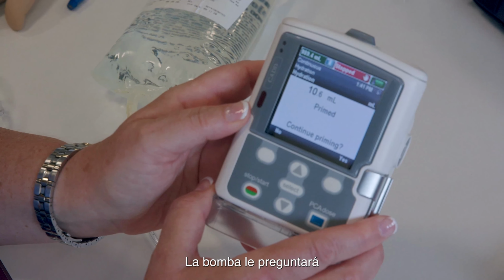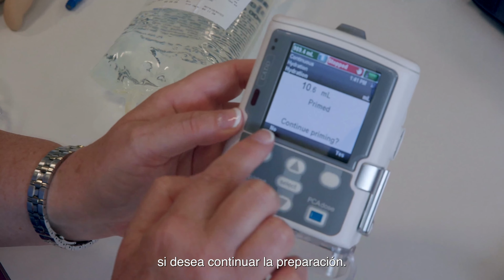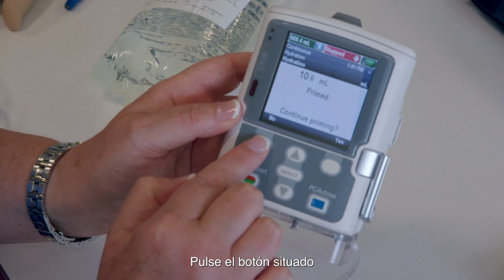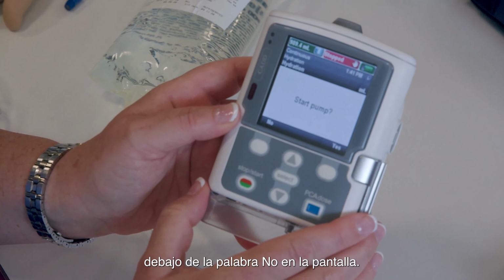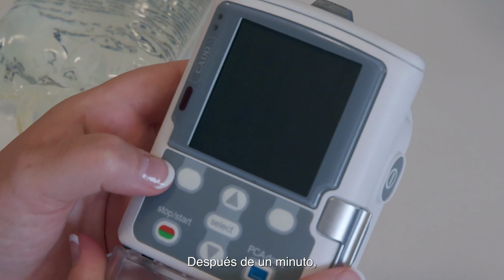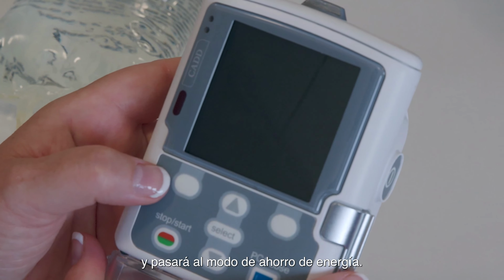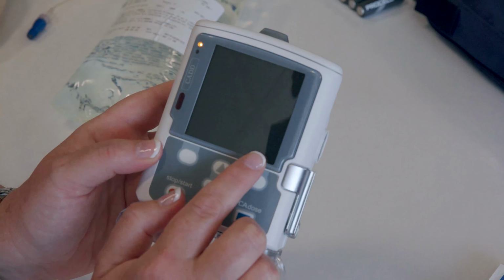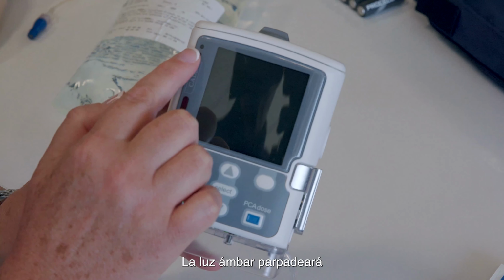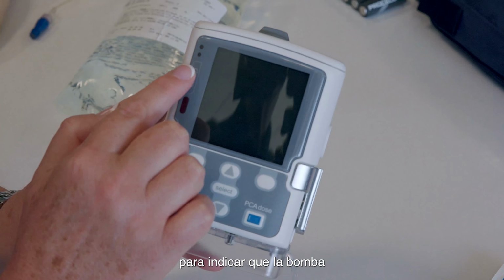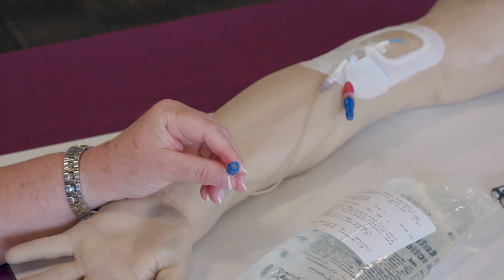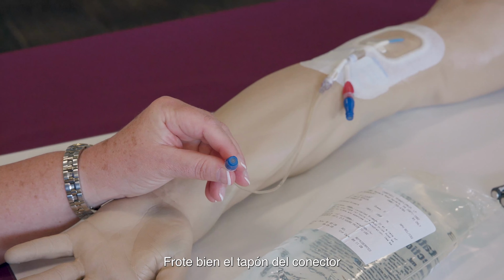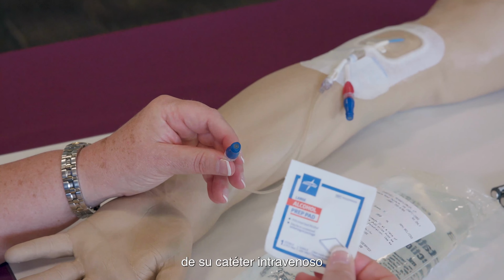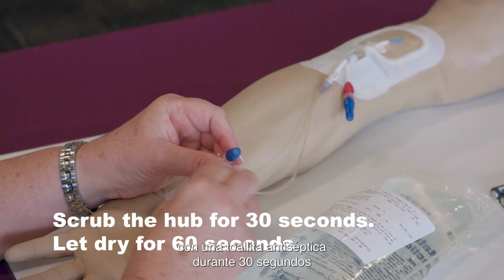The pump will ask you if you would like to continue priming. Press the soft button under the word No on the screen. After a minute, the pump screen will go blank, going into Power Save mode. This is normal. The amber light will continue to blink, indicating the pump is on but not infusing. Scrub the injection cap of your IV catheter with an antiseptic wipe vigorously for 30 seconds.